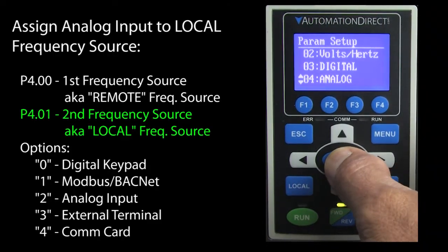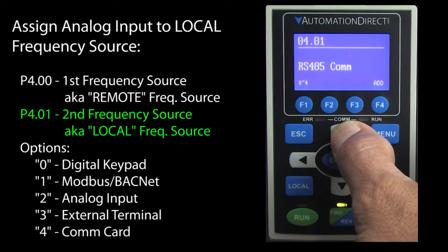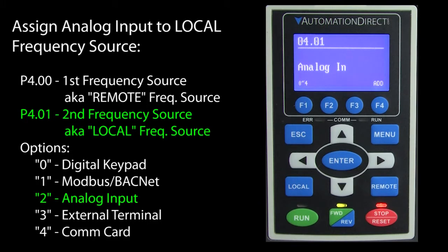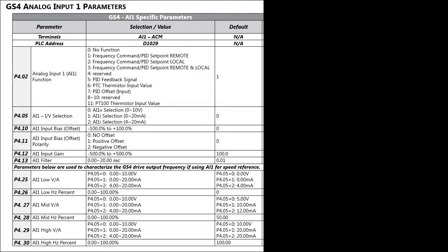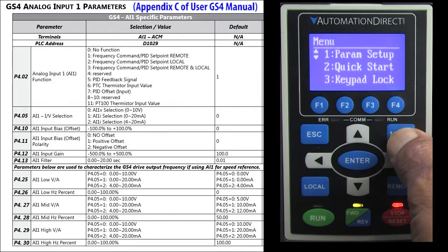We'll use parameter 401 to set the local frequency source to use the analog input as its reference. That will leave the remote frequency source available for something like a PLC to control the drive. Let's use that handy analog input reference chart in Appendix C as a checklist to make sure we don't miss anything.